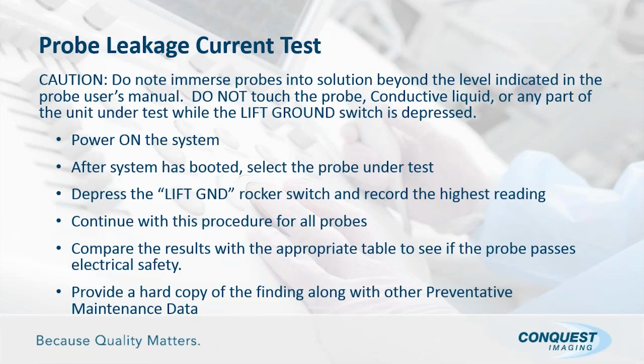And after that, do not immerse the probes into solution beyond the level indicated in the probe's user manual. If you don't have access to that, you can simply contact us. And bottom line is you need to make sure that the entire face of the probe is submerged. That does not mean the entire probe. I have actually had an in-service where they were asked to clean and electrically safety test the probe, and in order to clean it, they dumped it entirely into the cleaning solution.